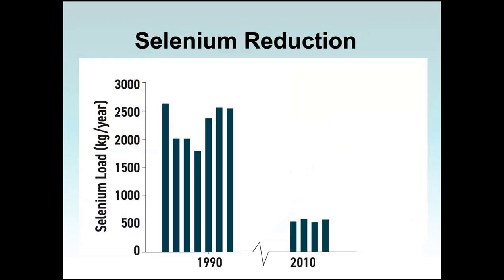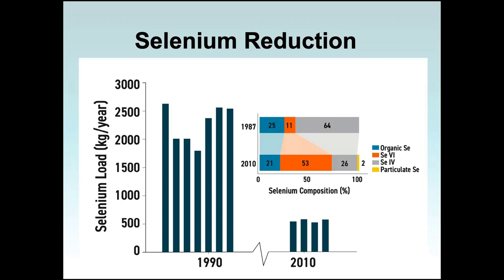The next big change was for selenium. This chart shows the huge selenium reduction at the five petroleum refineries. In the late 1980s and early 1990s, the collective selenium load was around 2,000 kilograms per year. By 2010–2011 it's just under 600 — about a 70% reduction in selenium load to North San Francisco Bay. The treatment plant improvements also changed the speciation of selenium discharged. In 1987, about 25% was organic, 11% was selenate, and 64% was selenite. After improvements, selenite dropped to 26% while selenate rose to 53%. This matters because selenate bioaccumulates much less than selenite, so not only was there a 70% reduction, but the selenium being discharged is far less bioavailable.